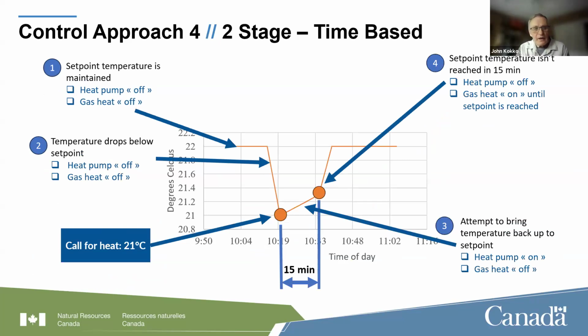Then approach number 4 is the control approach, the two-stage time-based. And what that says is, the house is coming along. It drops down to the heating turn on point for heating. The heat pump comes on, and it's given a certain time to see if it can hit the set point again. So in this example, it's 15 minutes. It could be 10 minutes. It could be half an hour. It's up to whoever is setting it up to decide what that time frame is.